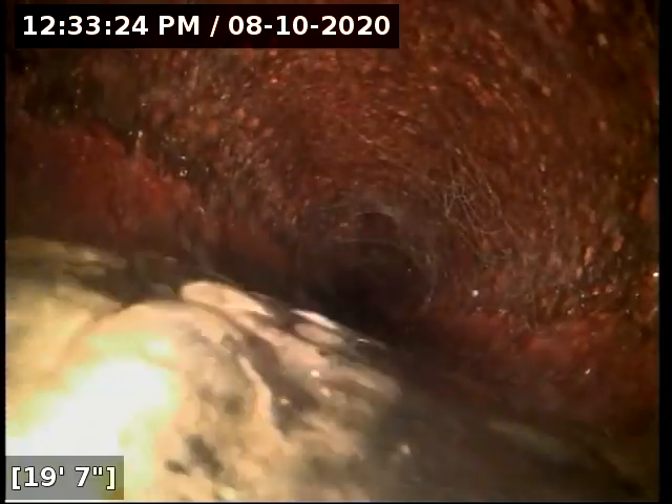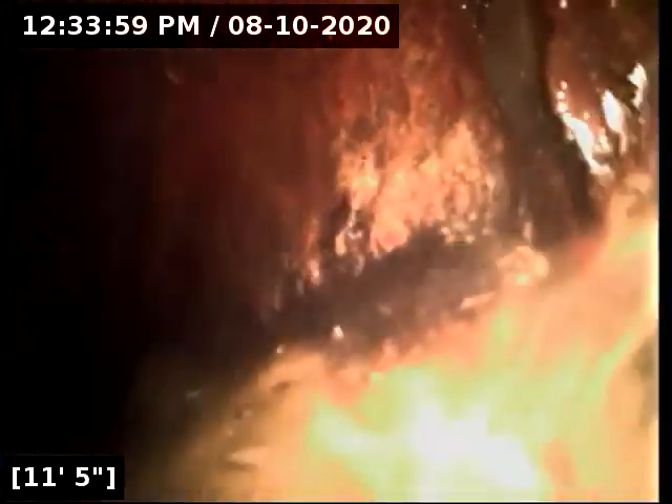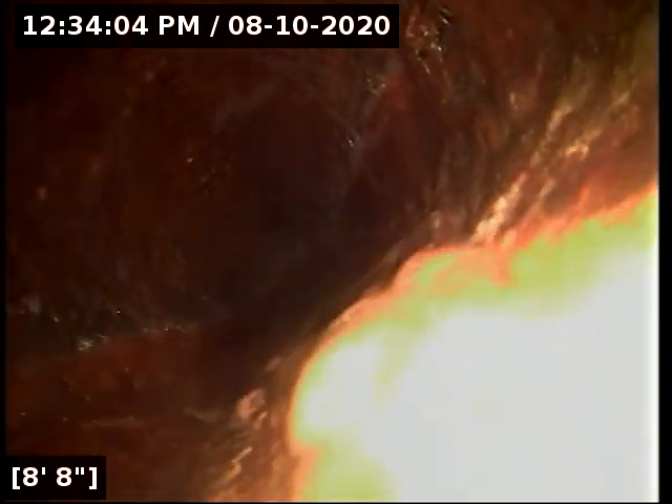Cleaning it is going to increase the diameter of the pipe by almost an inch. You've got some spots here where my camera is going to scrape some junk loose. A lot of it looks like it's probably a combination of sludge and paper products. I would recommend cleaning the sewer line out — there's some more that's going to break loose. Getting another look at the sewer line, I'd re-scope it and make sure that the pipe bottom is not rotting out on you. That can happen — or it will happen eventually in cast iron. Sometimes you get square spots in the flow line where the pipe starts to trough, where the metal is being eaten through and debris will get stuck down into it. There are just a lot of areas here where the pipe diameter looks like it's gone from four-inch down to as small as three-inch.